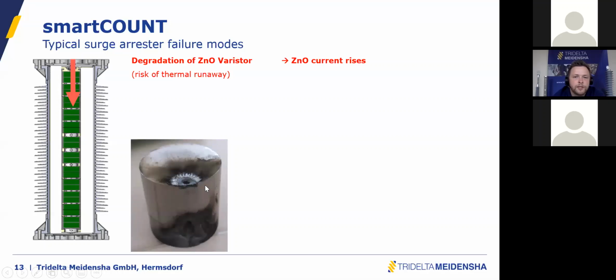First thing we always talk about and we always consider when it comes to surge arrester monitoring is the degradation of the zinc oxide varistor, which has been the classical case for years. You have to pay attention that your MOV blocks keep their health, and if they don't, the zinc oxide current rises and you run the risk of a thermal runaway. You have to pay attention. This is one of the most discussed failure modes, even if it's not the most common failure mode anymore, because surge arresters and zinc oxide blocks have been becoming highly reliable in the last years.